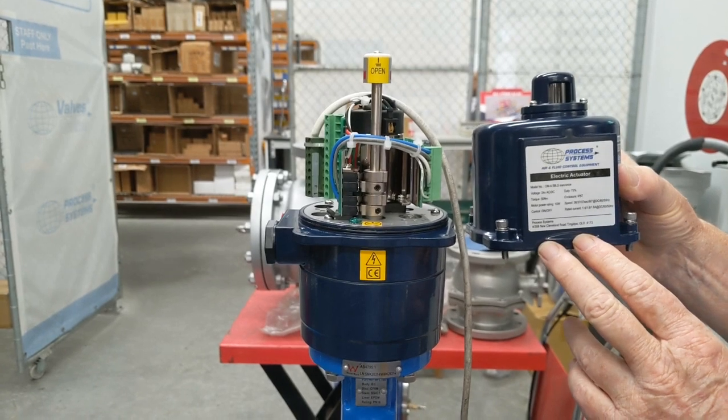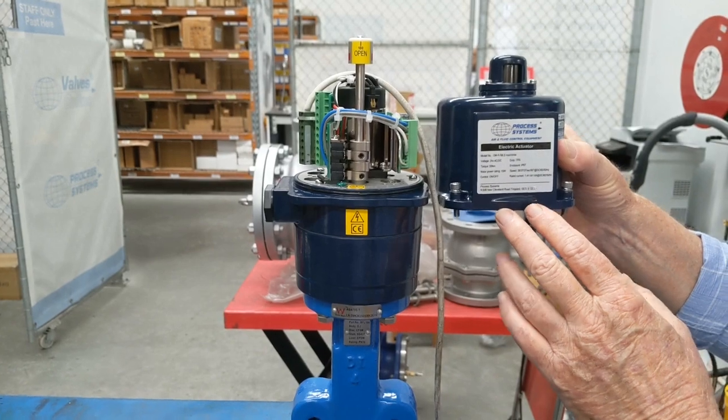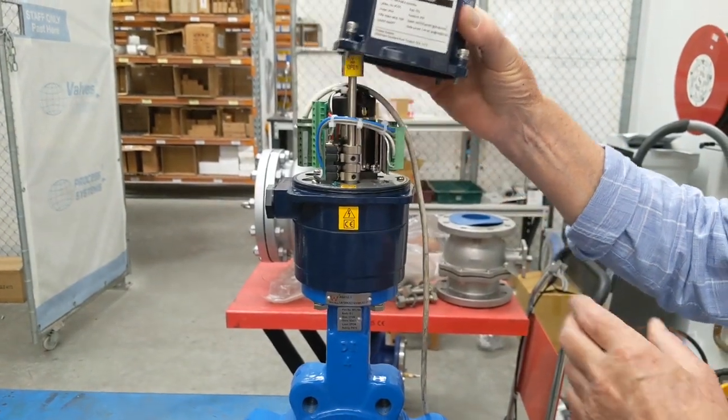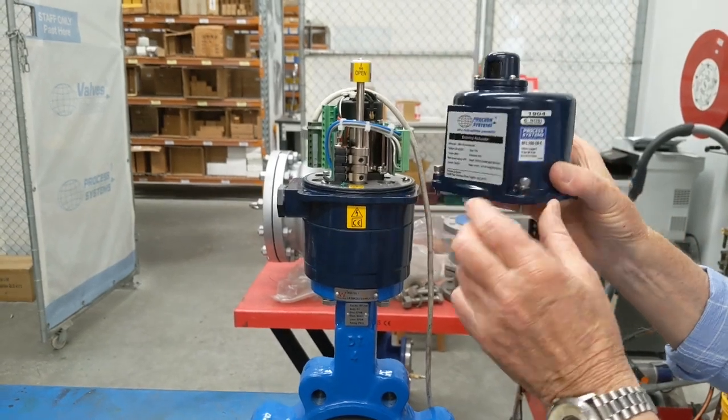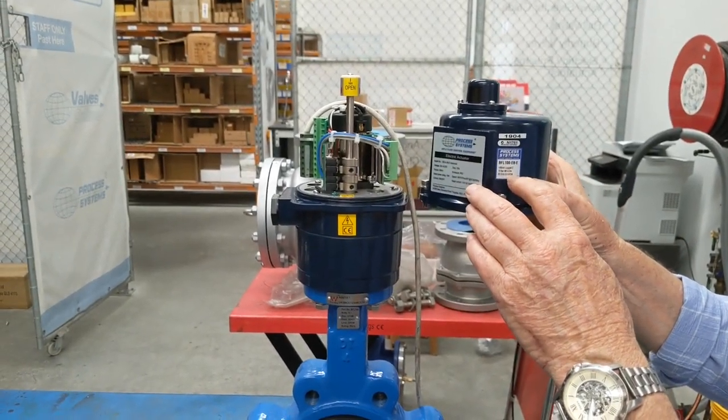It has a 50 Newton meter torque output and a 75% duty cycle, so it operates 75% of the time with the balance for heat dissipation, because it's a fully enclosed unit. It comes with our ATEX certification, batch coding, and part numbers are shown here.